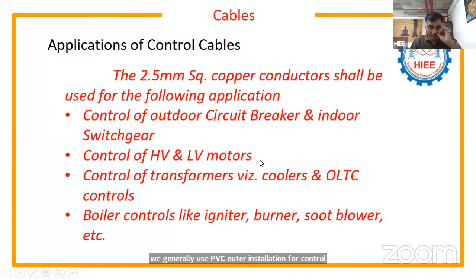Applications of control cables: I told you, control of outdoor circuit breakers. Generally in the electrical system, guys, an electrical system is an interconnected system. If you want to design any electrical system, you should understand all the components, not only cable. If you understand only cable and transformer, you cannot design the system. You have to understand all the electrical components like breakers, current transformers, potential transformers, relays, transformer selection and sizing, cable selection and sizing, battery and battery charger.